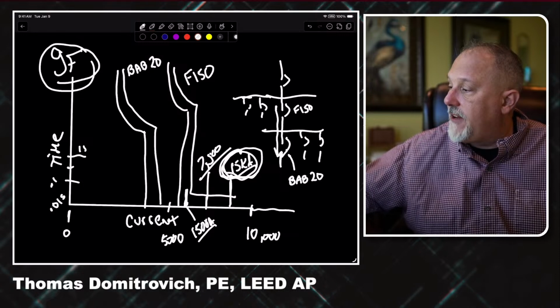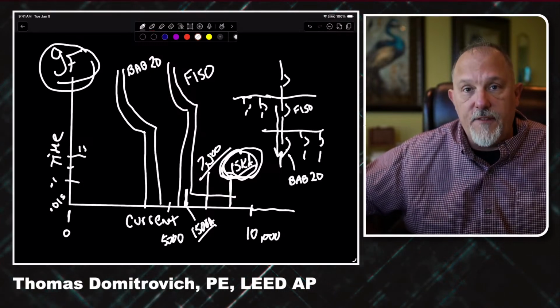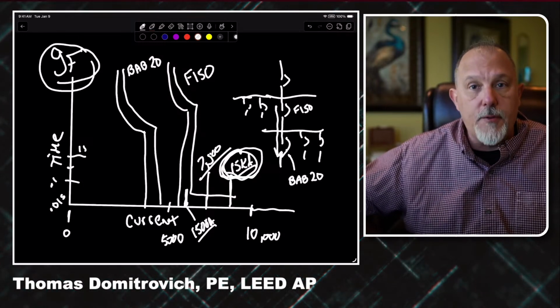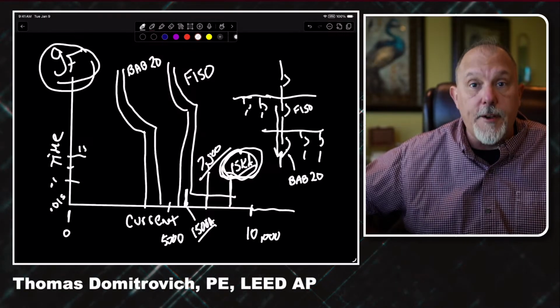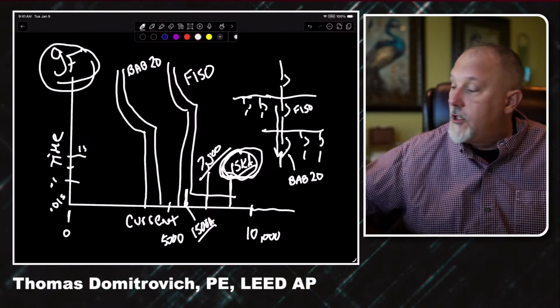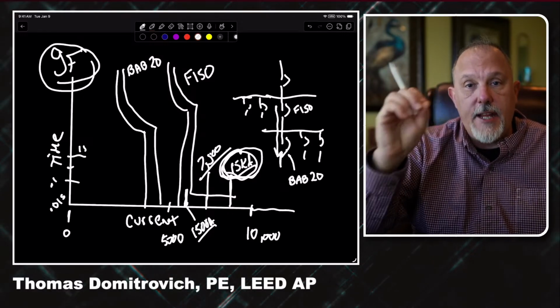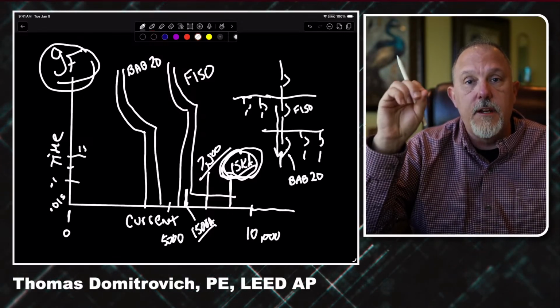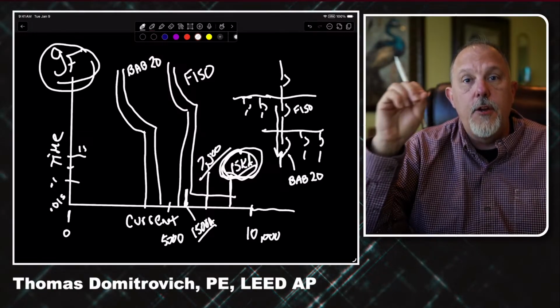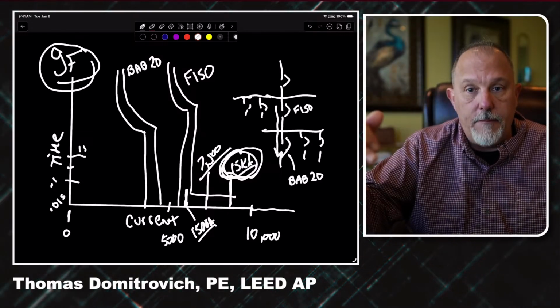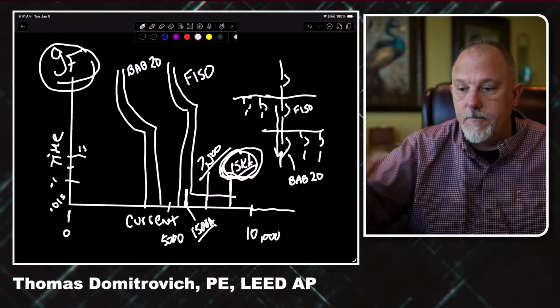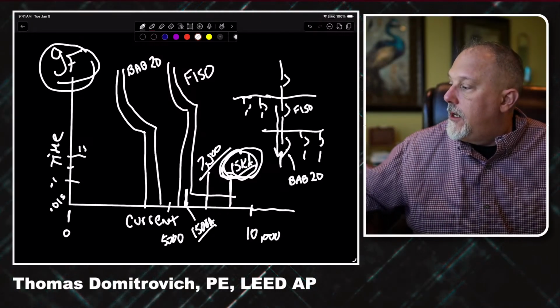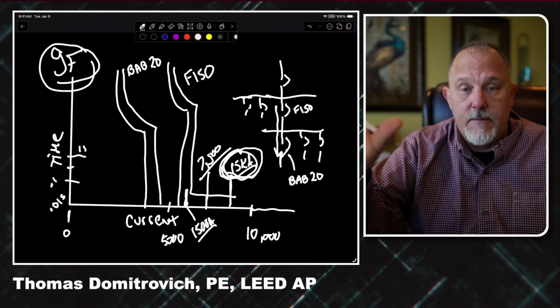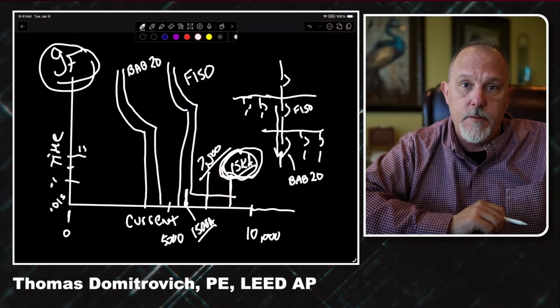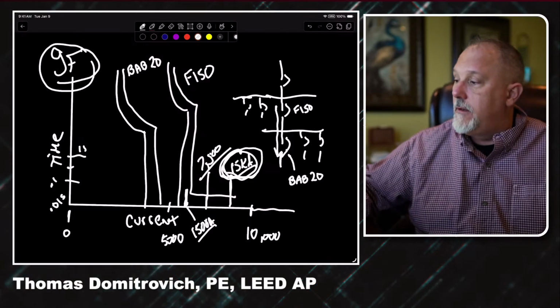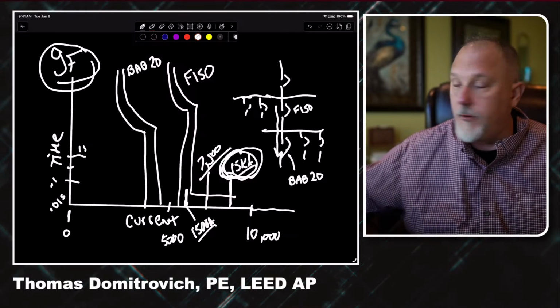And if I put 7,500 amps through a BAB20 and an F150, I know they will both open. They will not even coordinate. So I need to understand how the overcurrent devices will respond to currents passing through them. That's a critical piece of the puzzle. And that is a fact. That is per the code, and that is per the language of the code.